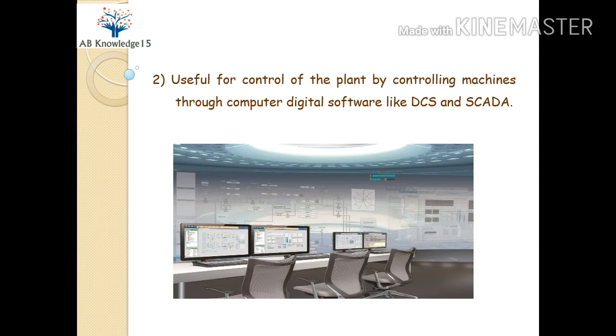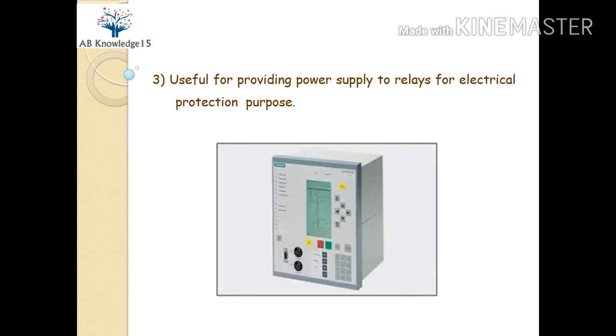The second use is for control of the plant by controlling machines through computer digital software like DCS and SCADA. These software systems are generally dependent on AC power under normal conditions. However, their power supply sources are generally provided by UPS panels. In case AC power fails, the battery banks come into line with the UPS panel and supply power to these computer software systems so you can control the plant even without AC power supply.